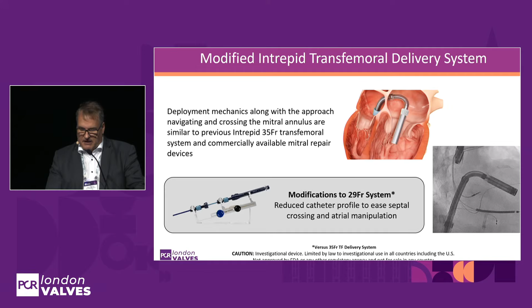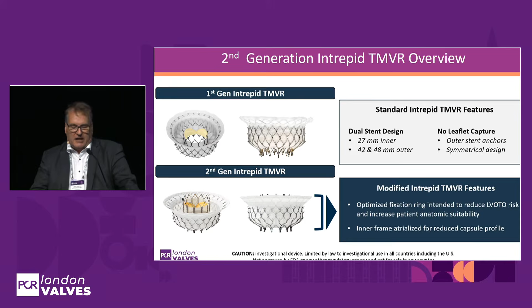And what you can appreciate is that the shoulder of the device and the sealing area has been reduced by some millimeters in order to open the LVOT clearance for the device. At the same time, the valve moved up some millimeters into the atrial space, giving this additional clearance and reducing the impact in the left ventricle. So while the inner stent with 27 millimeters stayed the same, also the outer stent design has a difference, as you can see here, with a flatter shoulder beneath the landing zone. And again, there is no leaflet capture.